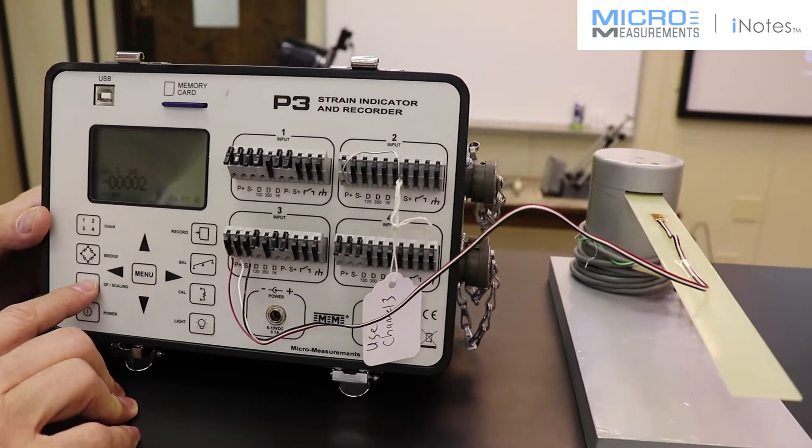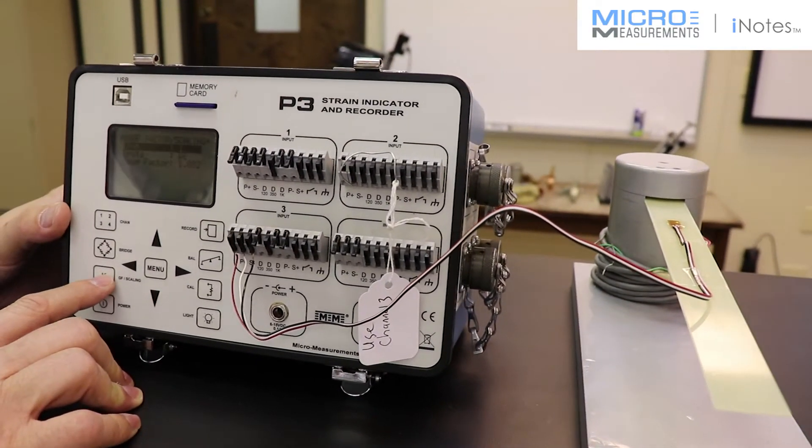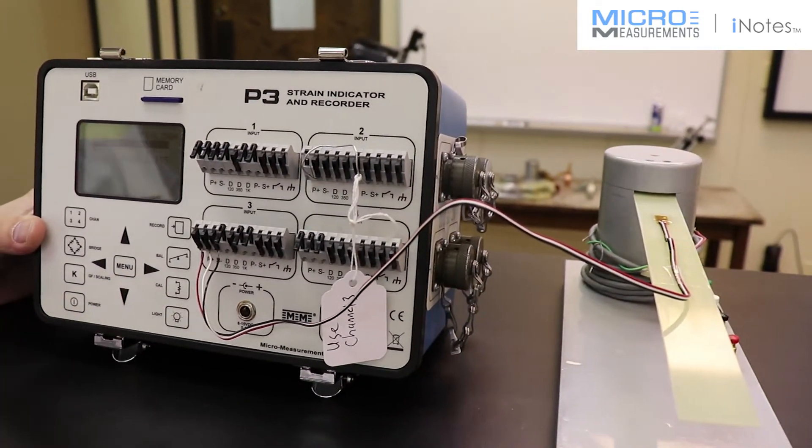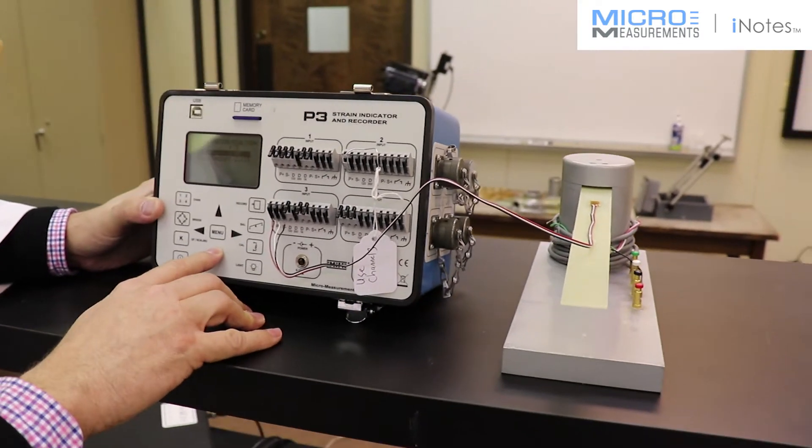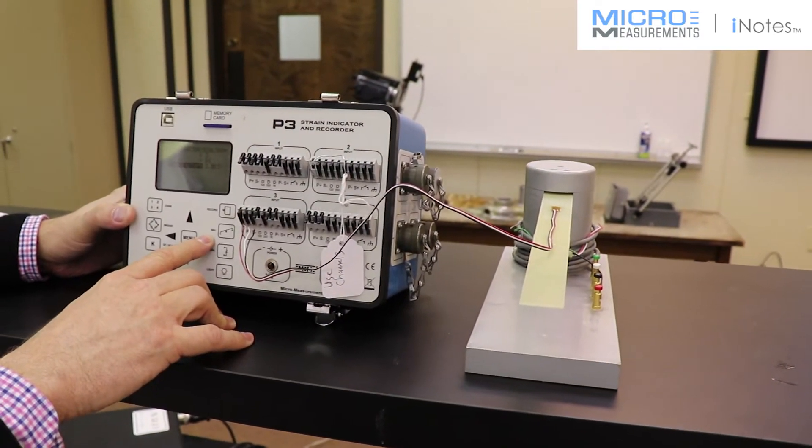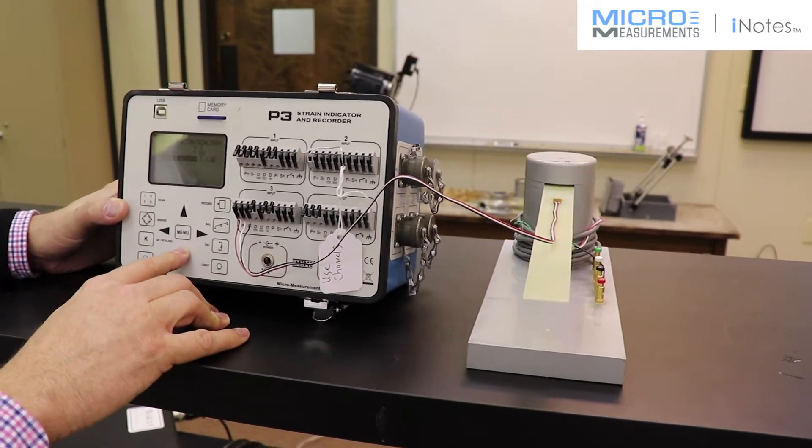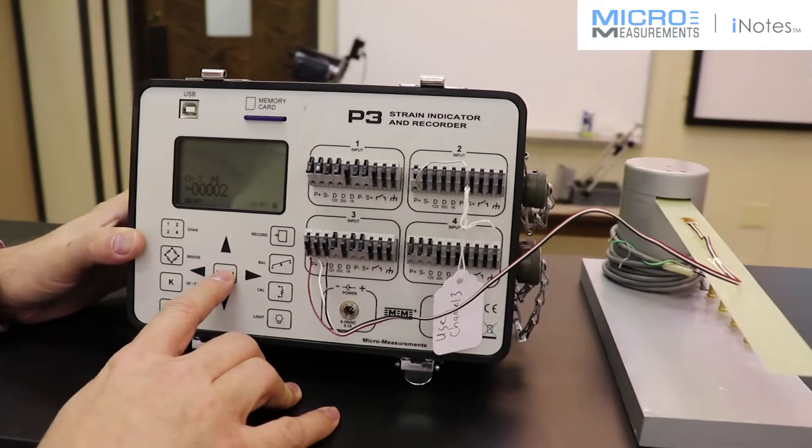The next step is to set the gauge factor for the strain gauge. Let's go to channel 3, 2.120. I'll just arrow down, go up, over, and menu to get back out of it.